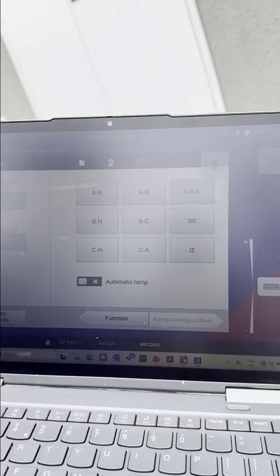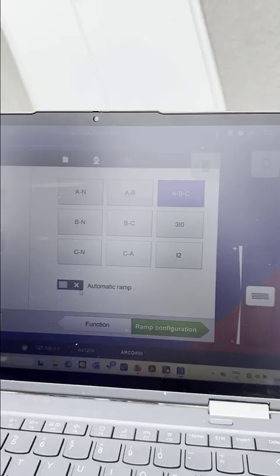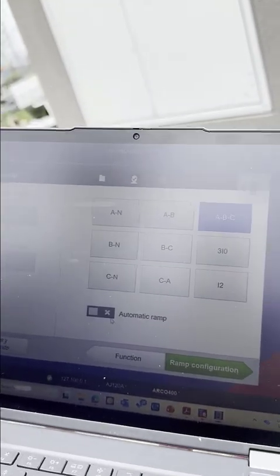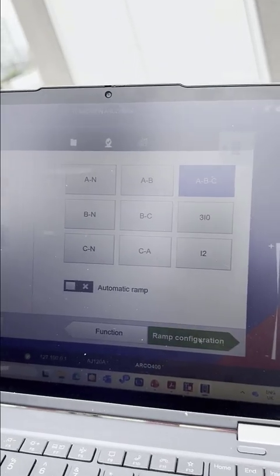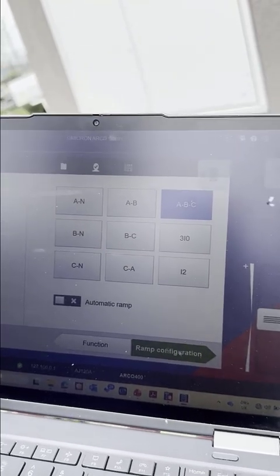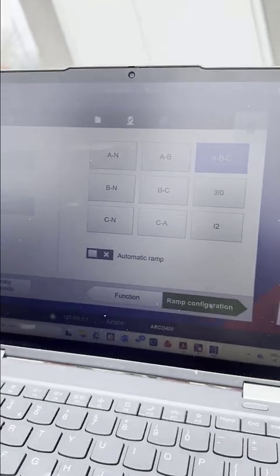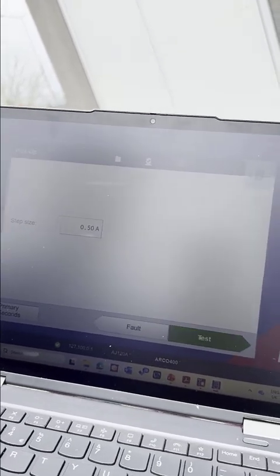For example, if I am going to test the overcurrent, we can select the 3-phase or the phase-to-phase. For example, I will select now 3-phase ABC. Also, you can enable the automatic ramp if you need to assess this test result automatically, or manually with the button. But just because some relays don't have the start contact in the pin out configuration, you can only see the LED of the relay in the front panel, and you can make manual backup. Then here you can define the step size as 0.5 ampere. Then you can go for the test.